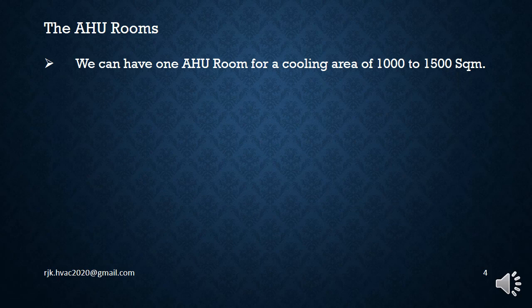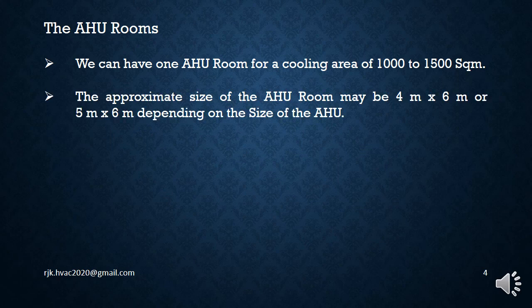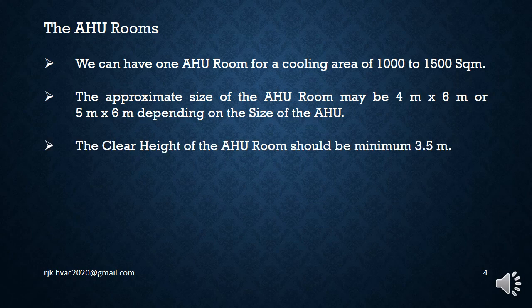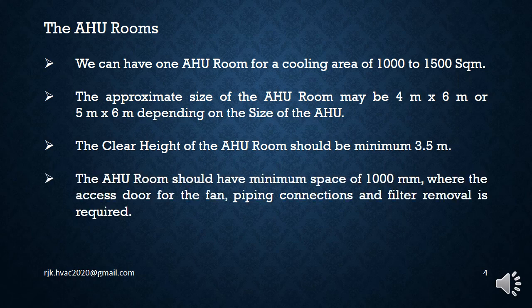We can have one AHU room for a cooling area of 1000 to 1500 square meter. The approximate size of the AHU room may be 4 meter by 6 meter or 5 meter by 6 meter, depending on the size of the AHU. The clear height of the AHU room should be minimum 3.5 meter. The AHU room should have minimum space of 1000 mm where the access door for the fan, piping connections and filter removal is required.